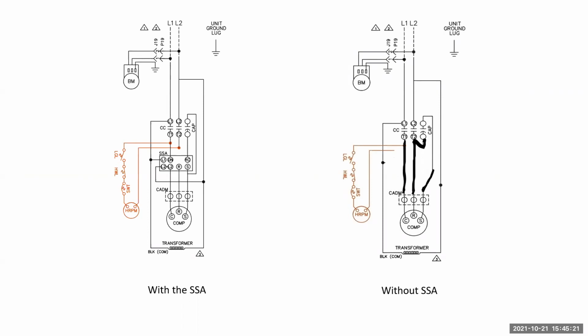Over here on the left-hand side is a wiring schematic, a cutaway of one with the SSA wired in. And then on the right-hand side, you have the removal of the SSA. It's just like your standard compressor wiring, the capacitor, run, start, common. And we can send this to you if you need us to.